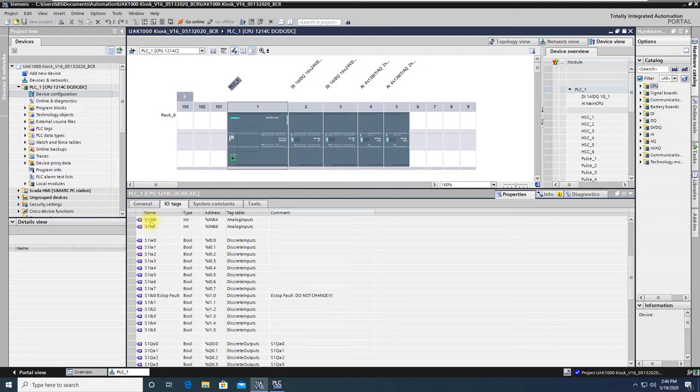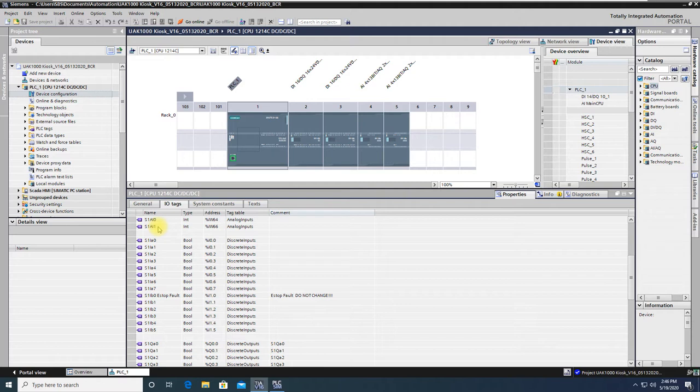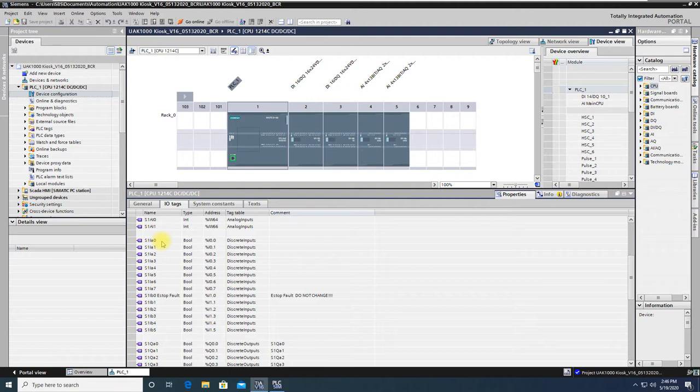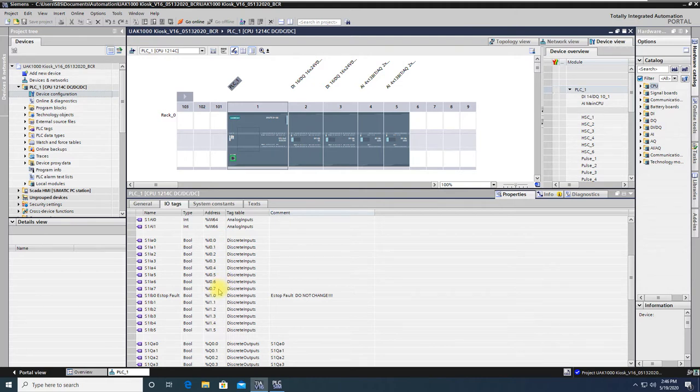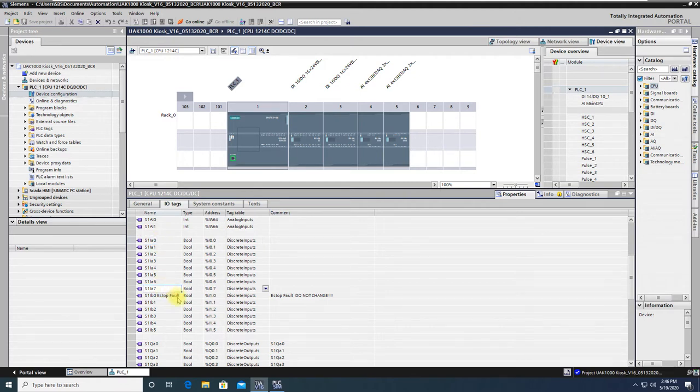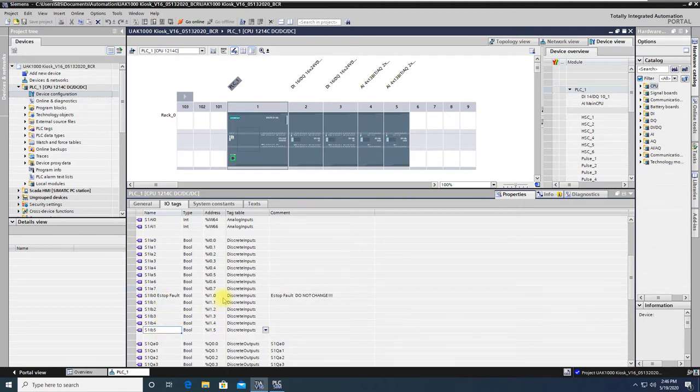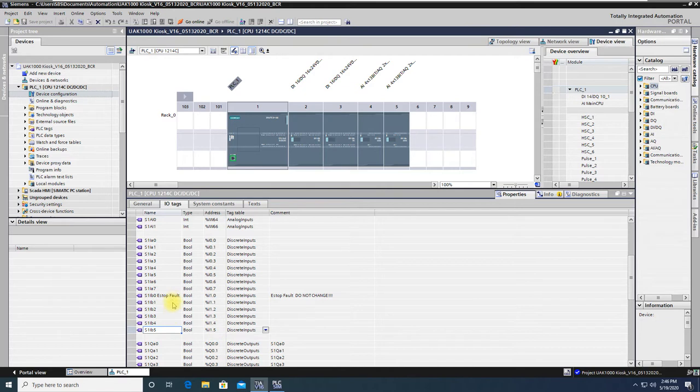So slot 1 has an analog input 0 and an analog input 1 that is available for you to use in your programming. Also, there are 14 discrete inputs. So in the naming of it, we called it a slot 1 input, I for input. And since Siemens uses addressing in groups of 8, or a byte-oriented addressing scheme, we followed that pattern with our input A group, bit 0 through bit 7. Then you'll follow into a B group, bit 0 to 5 shows up here, because out of the 14 inputs, only 6 are found on that CPU.